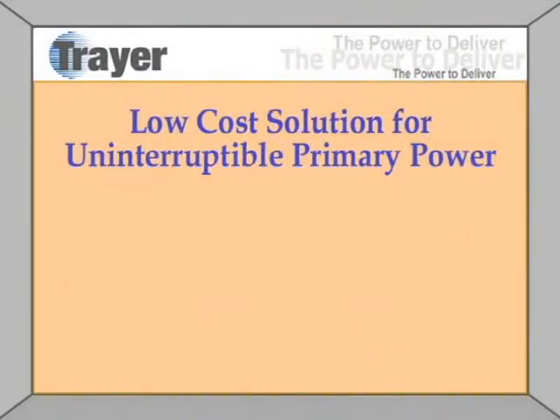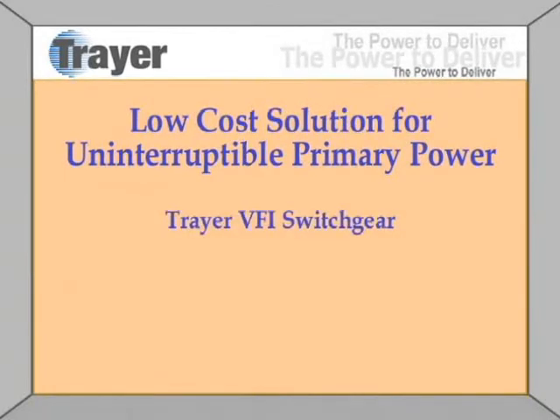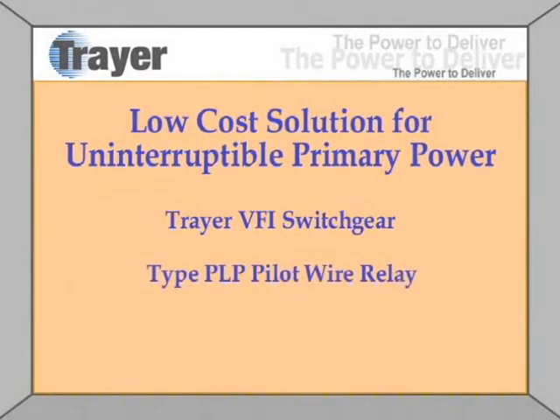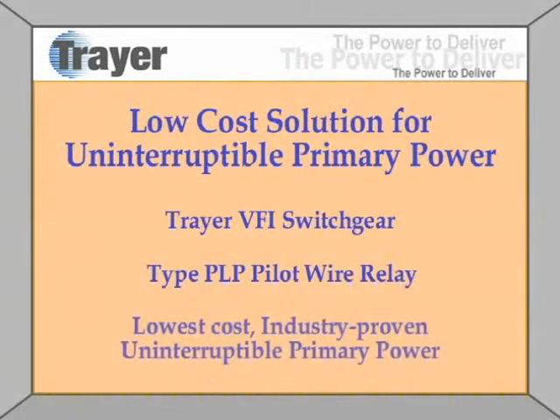So there is a solution. There is a low-cost solution for uninterruptible primary power. It's available today. It's been available for 60, 70 years. It's a combination of the Trayer VFI switchgear and Trayer's own PLP pilot wire relay. This combination is the lowest cost, industry proven, uninterruptible primary power solution, and we've got them out in the field working.